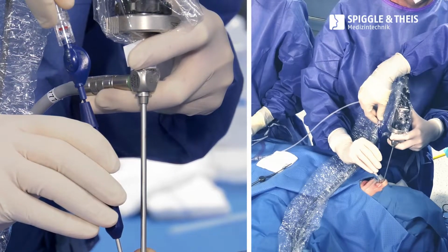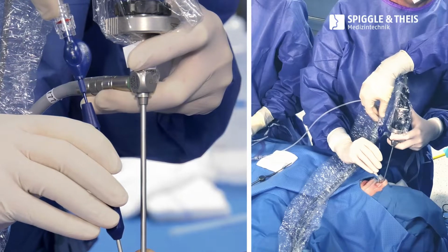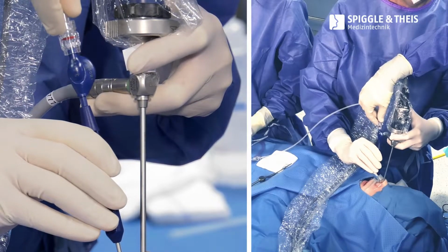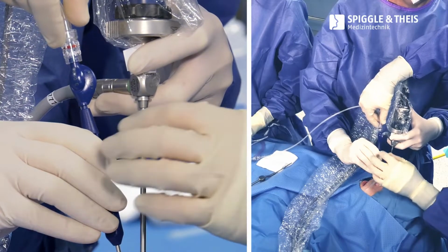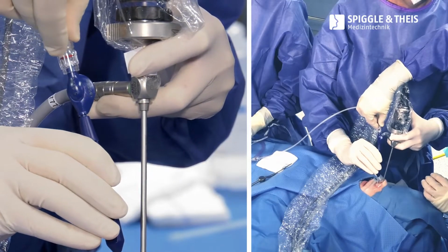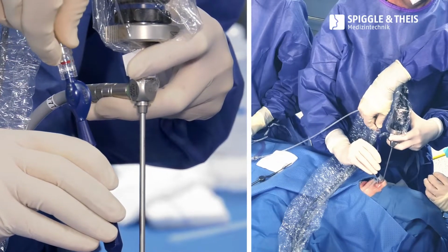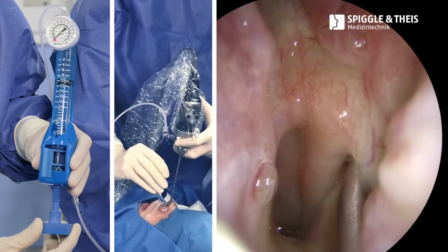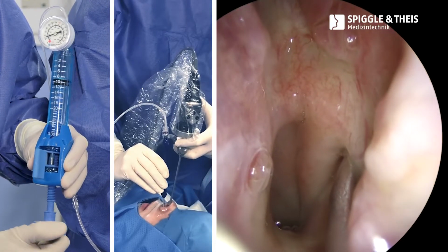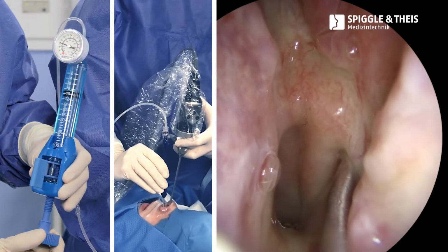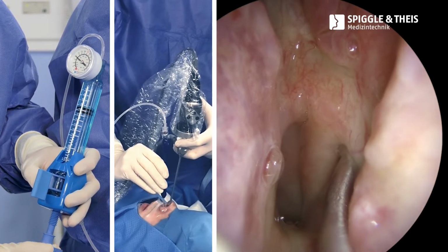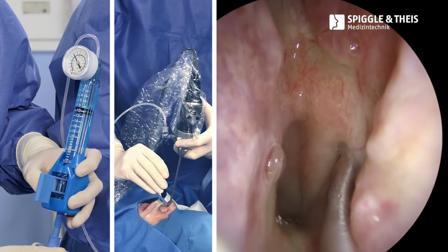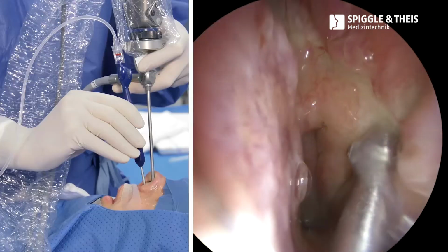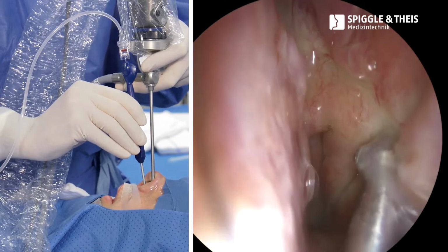Excessive resistance will indicate a wrong insertion of the inserter and therefore the possibility of rupture of the balloon at this point. Inflate the balloon by keeping the pump key closed and turning the plunger clockwise until reaching a pressure of 10 bar in the pressure gauge. This pressure must be maintained for 2 minutes.